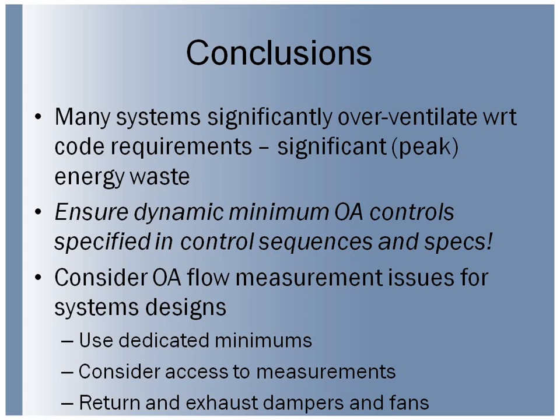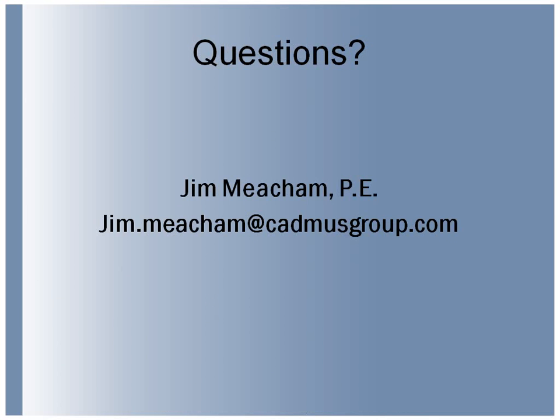We still see a lot of projects that come through that don't have a sequence that specifically defines that mode of operation for our systems. And then we need to be cognizant as an industry of how that minimum flow rate is going to be controlled. Using the dedicated minimums, making sure that we have access. There's a method for taking the measurements and getting accurate measurements, and how the implications of using return fans or exhaust fans in the different damper systems for how that is going to be able to be controlled in the field. We need to bring that into our day-to-day practice. That's it.